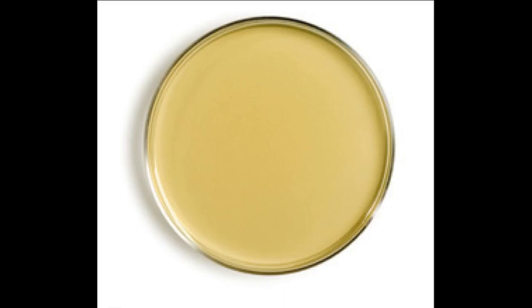After depyrogenation, the test material did not contain any viable microorganisms after 14 days incubation and hence meets the requirements of sterility. The test material has passed the sterility test. Packaging under class 10,000 clean room environment: implant transfer to class 10,000 clean room through dynamic pass box. A dynamic pass box is a cubicle box which has 0.3 micron HEPA filters, forward curve air blower, UV light, and interlocked doors located on both sides. This protects the controlled environment from being polluted while the transfer of material is taking place.